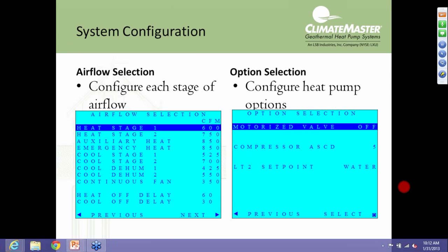The next item is the compressor anti-short cycle protection time. And the default is 5 minutes. You can't go any lower than 5 minutes. You can go up to 9 minutes.